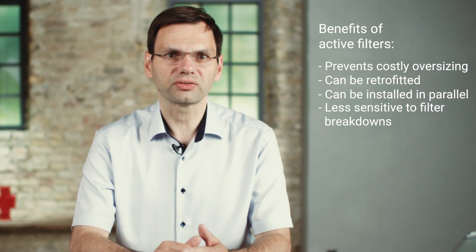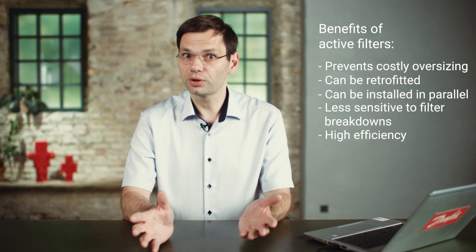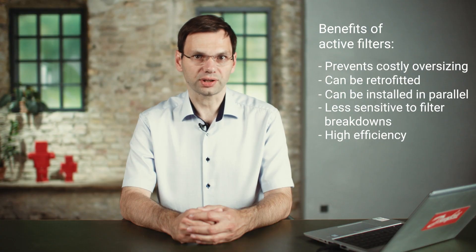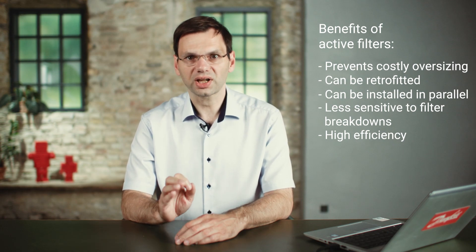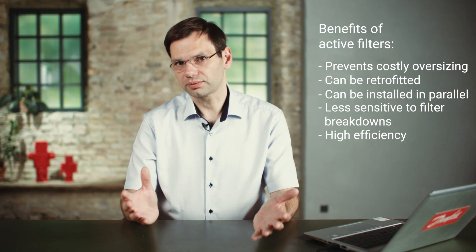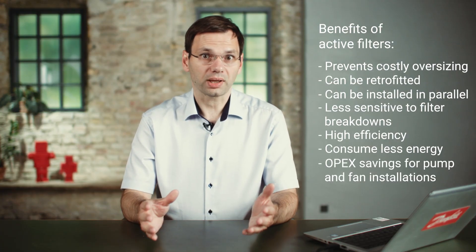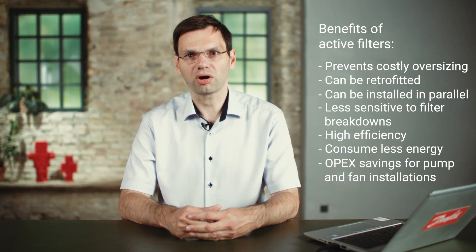Especially when modular active filters are in parallel, the efficiency of an active filter is typically around 98% at full load. Just like active front-end and low harmonic drives, the losses are almost constant due to the constant switching need, and losses are only generated when the filter is active. If the load is reduced, the active filter can go into sleep mode and save energy. For pump and fan installations running mostly at partial load, this constitutes a significant saving of operating expenses. Active filters do generate switching and common mode noise that need to be considered.